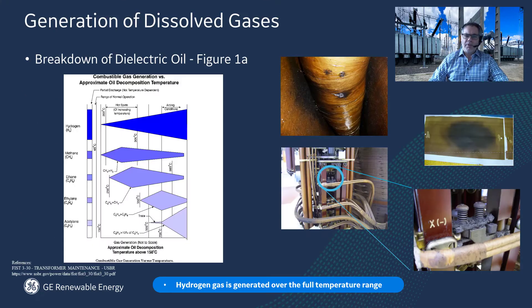As we know, hydrogen gas is normally produced under all fault conditions affecting the insulating oil. Monitoring for hydrogen gas is important as it's generated quickly and in abundance, as shown in Figure 1A. It's a key indicator to potential transformer issues caused by partial discharge, thermal faults, and arcing.